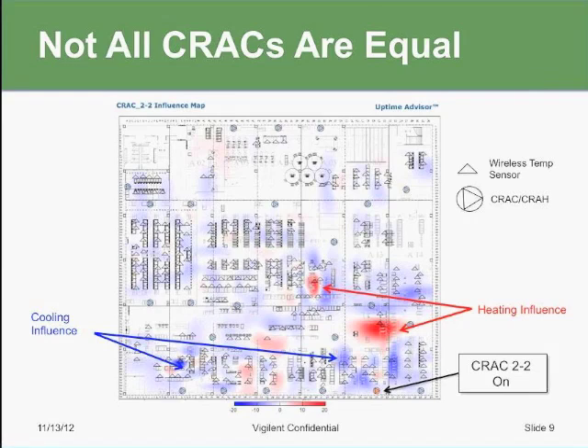It kind of goes back to the idea of if I install more cooling equipment, then I'm going to have more cooling redundancy in my data center, but that's not correct, and that's what this map is showing. So when this unit is turned on, it actually gets hotter in those specific locations. And why does it get hotter? Well, from what I just described, the excessive amount of cooling and airflow causes mixing, which causes the localized hotspots.